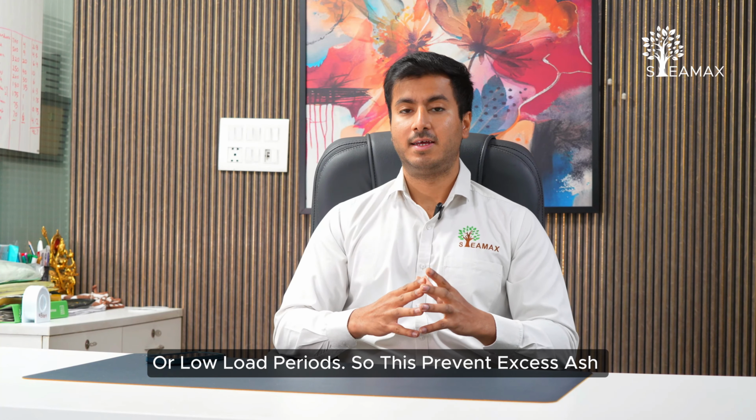Now, to prevent this ash from escaping into the environment, we add additional air pollution control devices such as a cyclone dust collector, bag filter or wet scrubber to keep the overall particulate emission within government norms. In addition to all this, we also recommend regular cleaning of the boiler tubes so that if any ash is still left inside the boiler tubes, it is regularly cleaned. This keeps the boiler running effectively and efficiently on biomass as well.